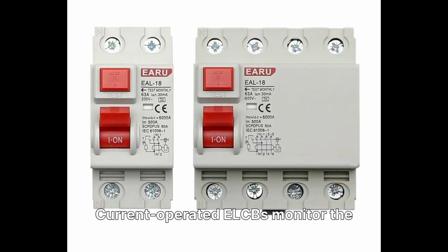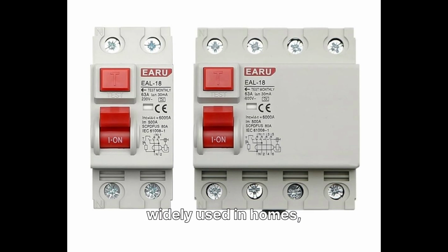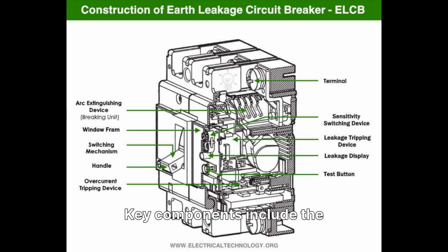Current-operated ELCBs monitor the difference between live and neutral currents and are widely used in homes, offices, and factories for their reliability. Key components include the current transformer that measures wire currents, a sensing circuit to detect imbalances, a trip coil that energizes on fault, and a switching mechanism to disconnect power.